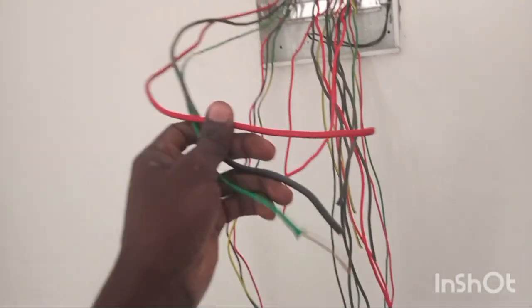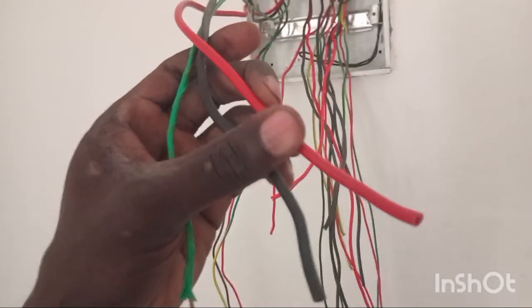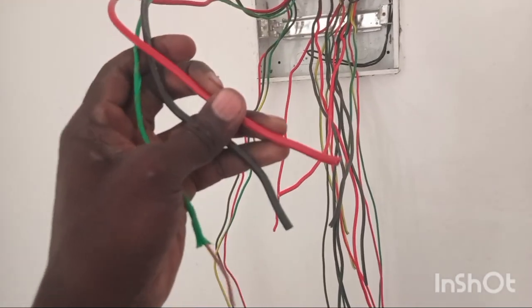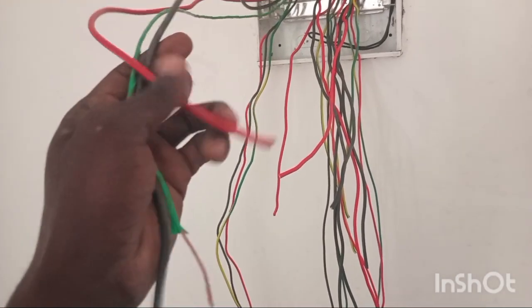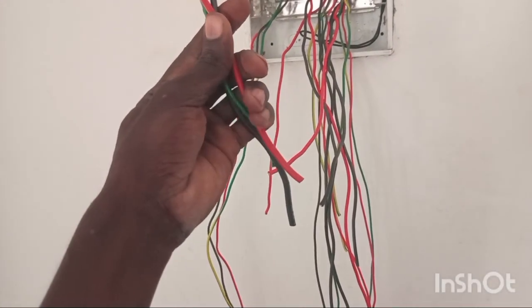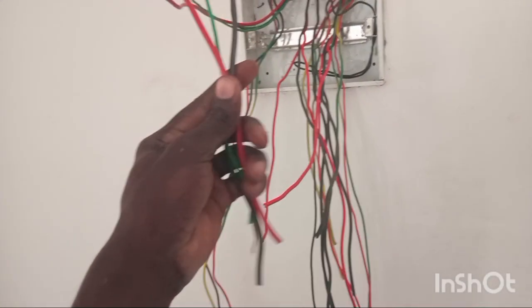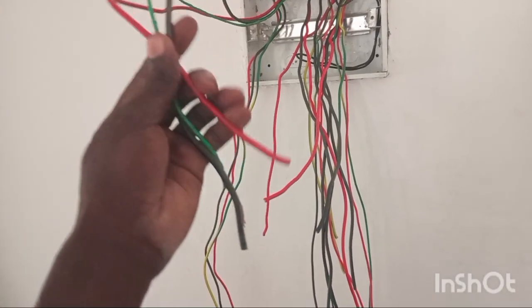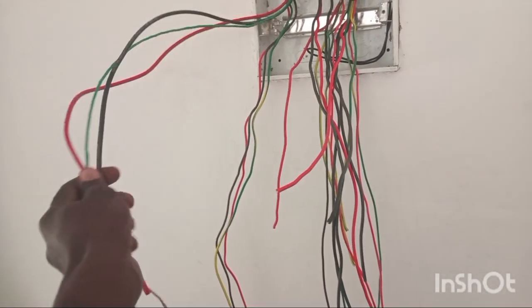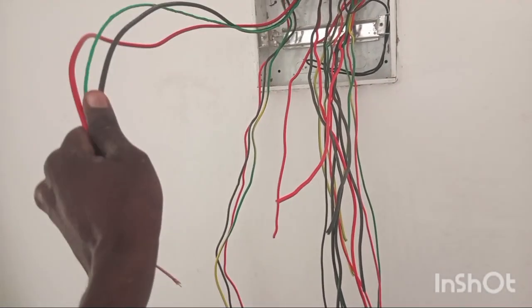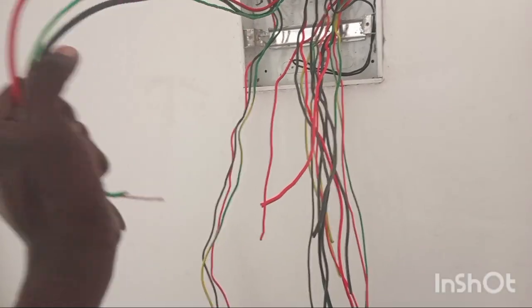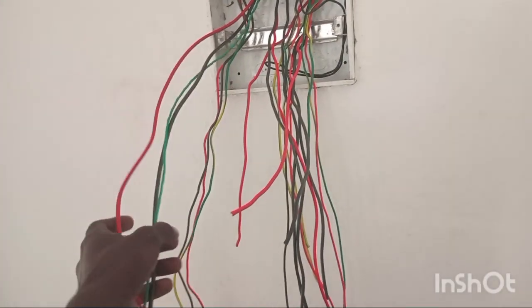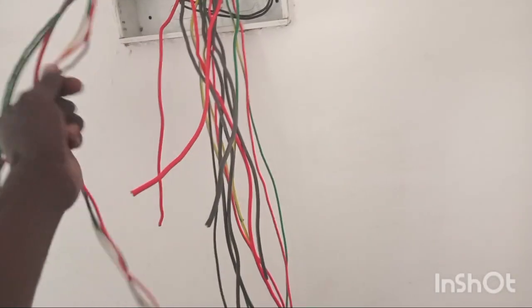We have the submain. As you can see, we are going to use the submain cable rated 6.0. So when the submain reaches the consumer unit, we are going to feed it to the double pole rated 63 amperes. Then we loop it with a connector to the other breakers. So we have also the sockets.